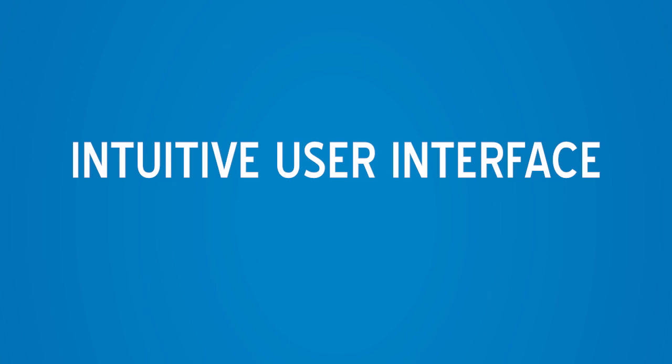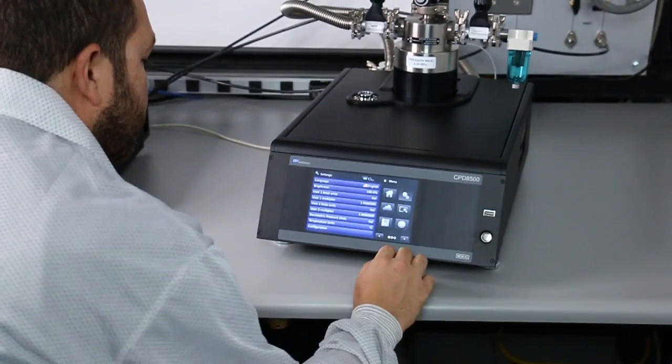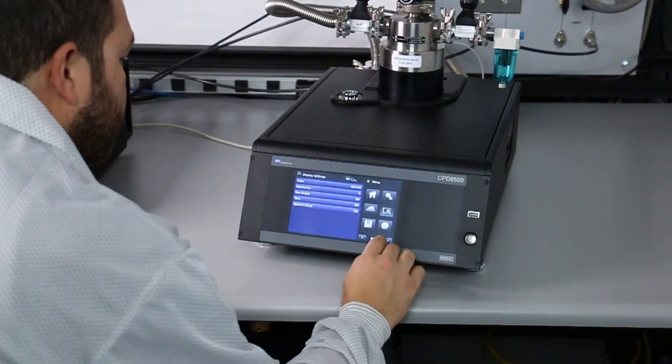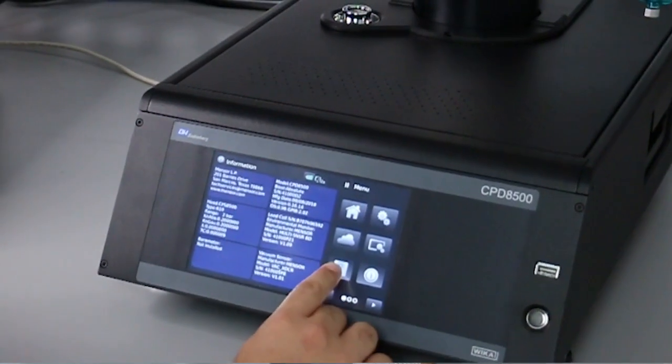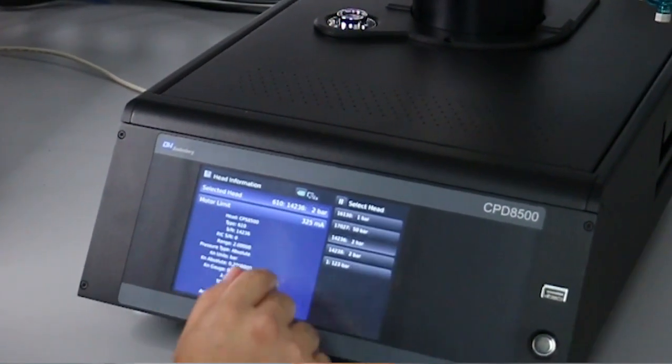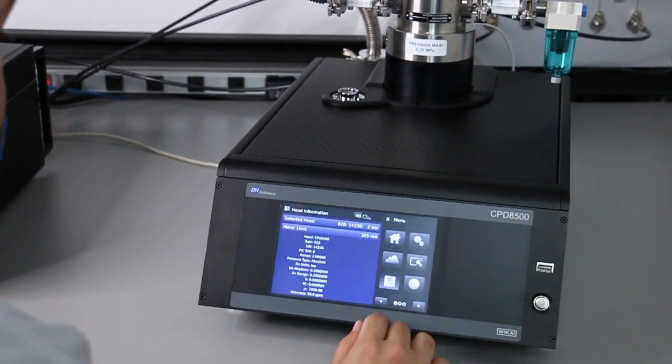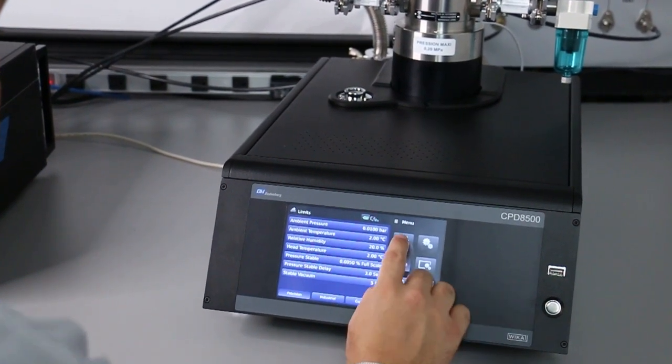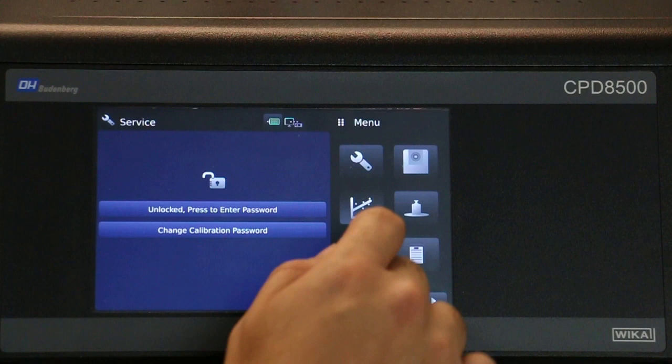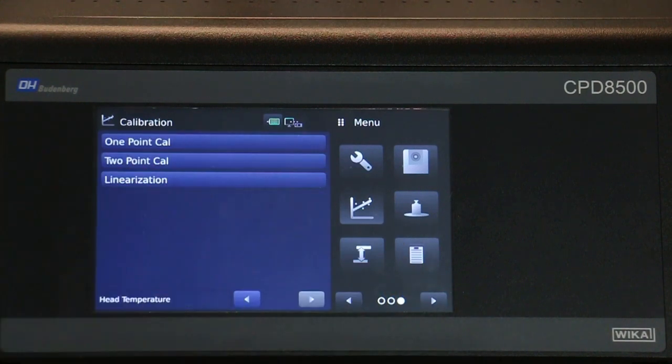The touch screen display shows all information necessary for operation. Navigation to set up screens and measuring head properties is easily achieved by touching graphic icons and following on-screen commands. In addition, all internal sensors are monitored and can be calibrated through the guided calibration menus.